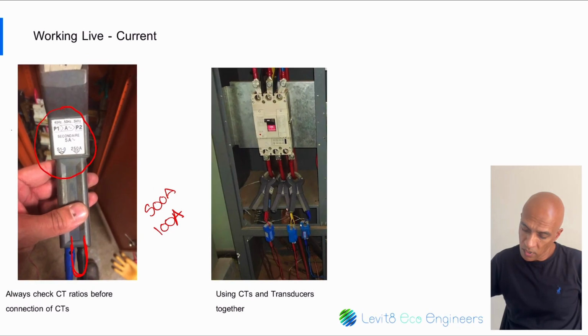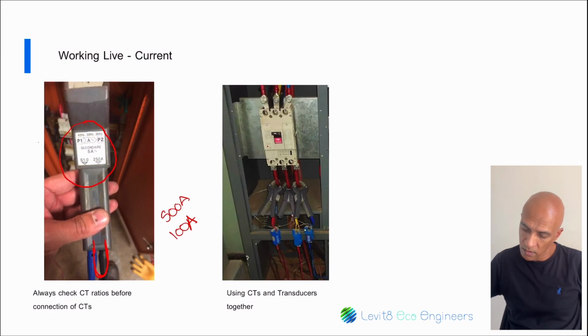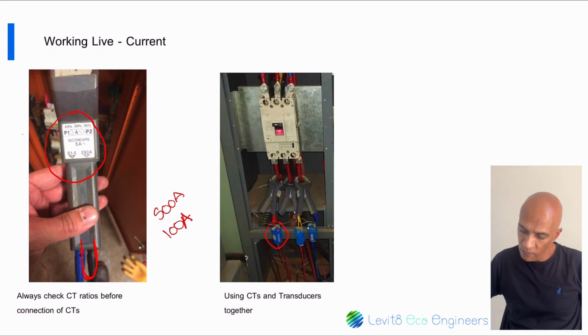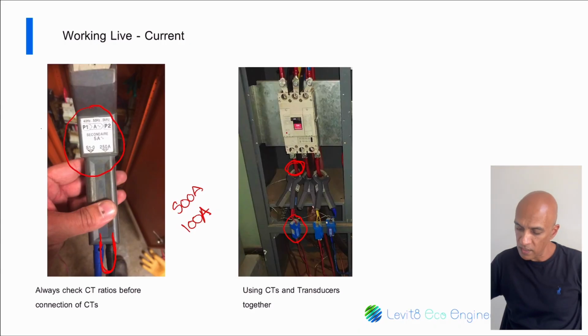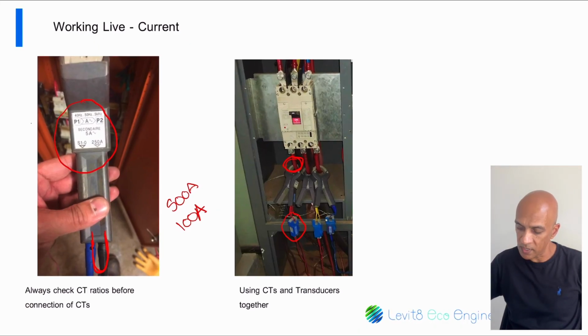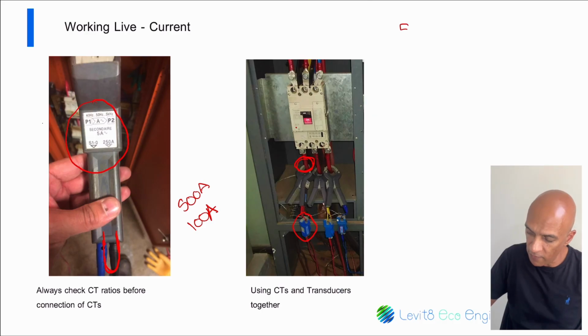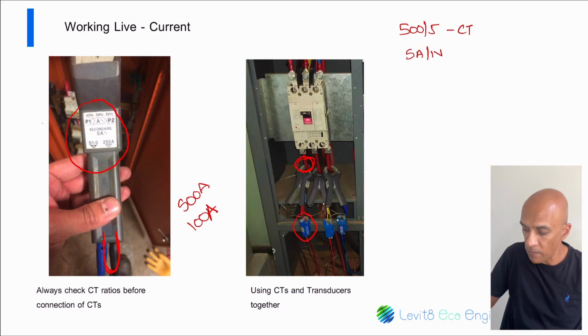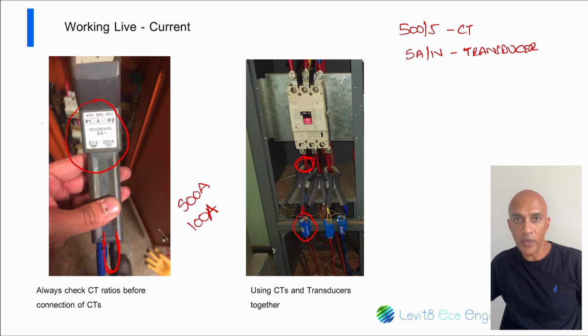In this photo, we have used the variable CT, and then we've connected the transducer. So the variable CT is connected onto the feeder cable, and then the transducer is connected onto the bridge piece. So assuming I had a 500 to 5 ratio on the variable CT, then I'm using the 5 amp to 1 volt transducer. So you understand how I'm actually doing my conversion of my voltages and my currents.